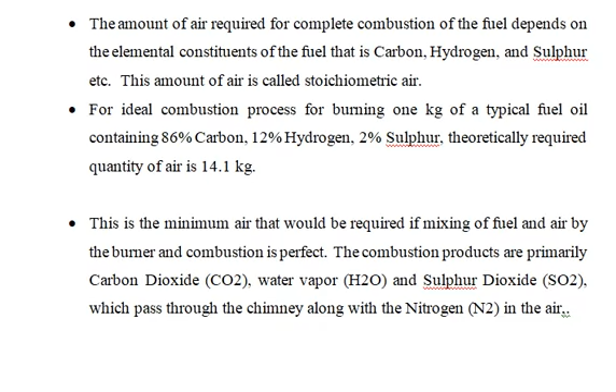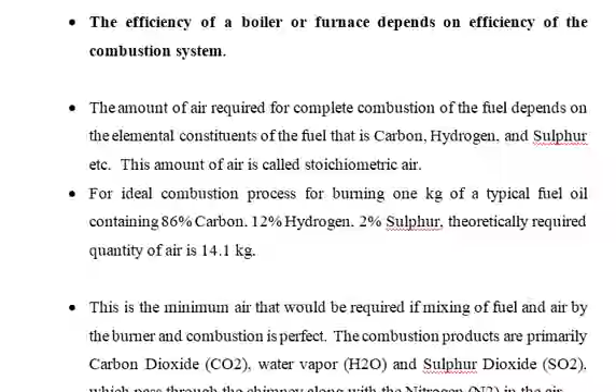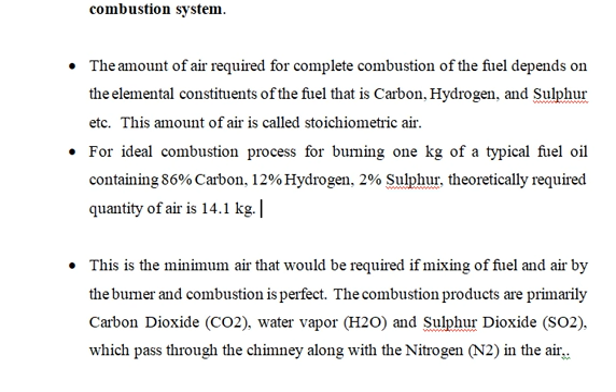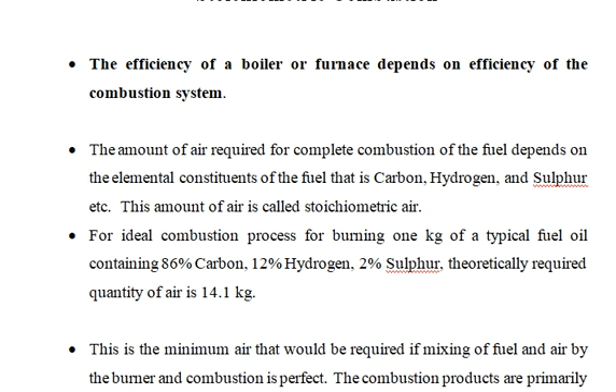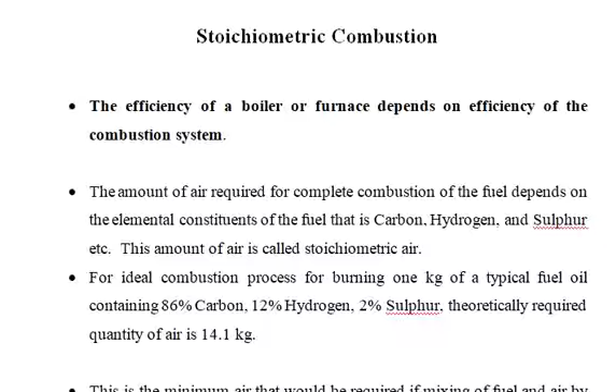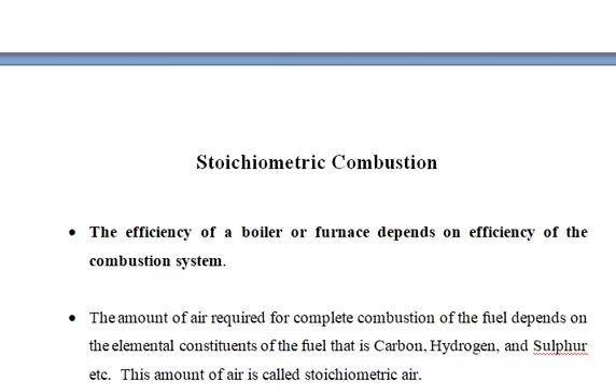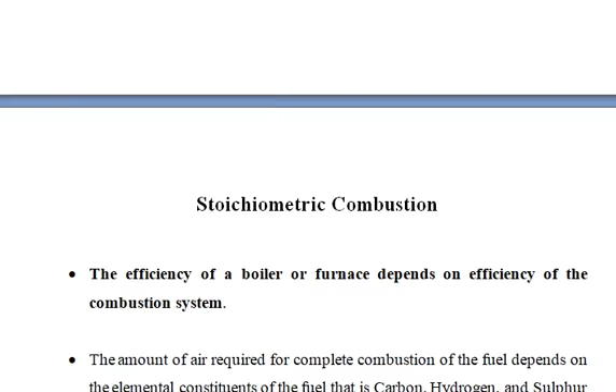And the last point: this is the minimum air that would be required if mixing of fuel and air in the burner and combustion is perfect. Combustion products are primarily carbon dioxide, water vapor, and sulfur dioxide, which pass through the chimney along with the nitrogen in the air. That means stoichiometric combustion means the minimum air required to combine with the carbon, hydrogen, and sulfur to generate gases and heat, and those gases pass through the chimney to the atmosphere again. The minimum air required for complete combustion is nothing but stoichiometric combustion.